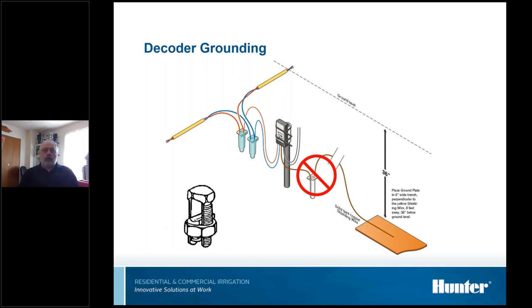The grounding material, and there's a couple of them. There's GEM and Powerset, the two most common ones. They're a metal oxide powder that we put down both underneath and on top of the grounding plates. It helps them conduct electricity. Obviously, it would work on a rod, except that we pound the rod in so the stuff won't get down where it needs to be. But that enhancement material greatly improves grounding when you're using plates. Typically, it will bring that resistance reading down to less than half of what it was originally, which is significant.